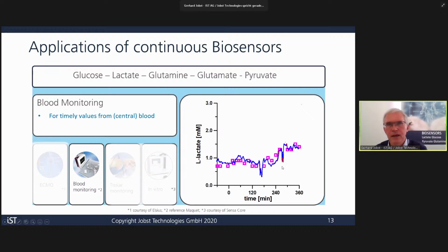The measurement curves of an actual online lactate measurement are shown here. This is a curve which was recorded already in 1994 in Austria, at the Graz Hospital of the Barmherzige Brüder, where we had students with the sensor in a direct bloodline.